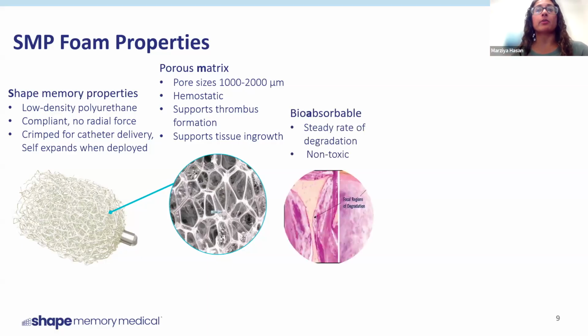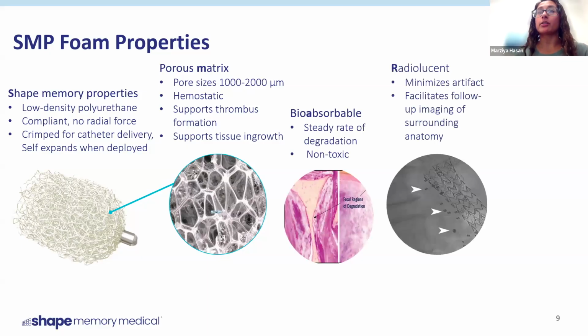Another thing is that our material is bioabsorbable. That just means that it'll degrade over time, and we have done some work to show that the byproducts from this degradation are non-toxic. Our material is also radiolucent, meaning that it is not visible under X-ray, and that's why we have the marker bands that I showed you in some of the previous slides. The marker band is the actual radiopaque component of the device, so that when the physicians are deploying these devices in the body, they know exactly where they are. The foam itself, however, is not radiopaque, but this is beneficial for us because it lets us image the surrounding anatomy without a lot of artifacts.